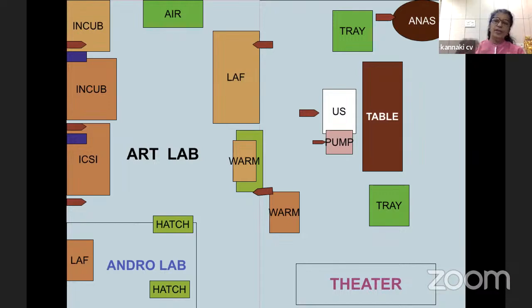All along your procedure, you must remember that the oocyte can get damaged if there are fluctuations in temperature. So if you keep the tube outside for long and then pass it on to the warmer, even a degree of temperature change or pH change can damage the oocyte and cannot give us a good result. So remember, from the time it comes out of the body till it goes into the laminar flow on the heated stage, the temperature should be maintained in a chain. So you have warmers, and it can go into the LAF, which will house the stereo microscope where they immediately see the oocytes, examine, separate them, and put them into the incubators.